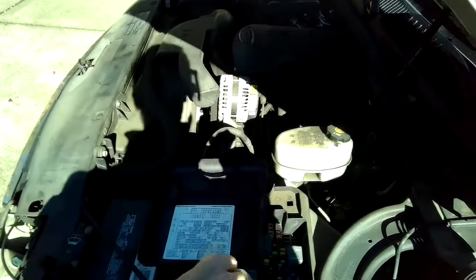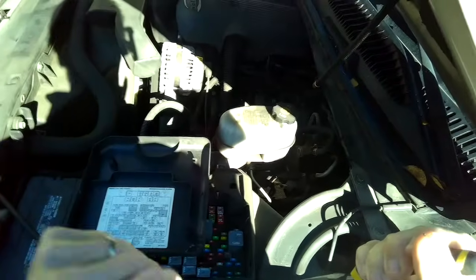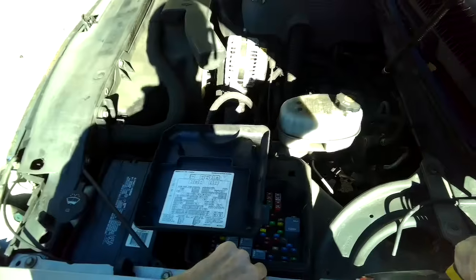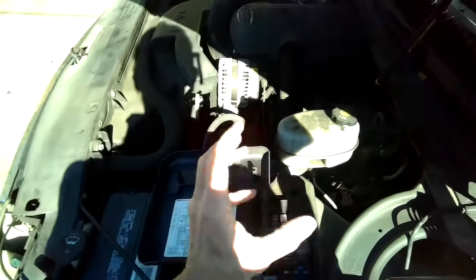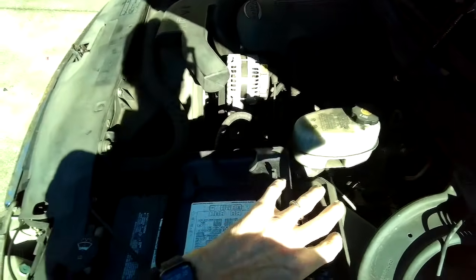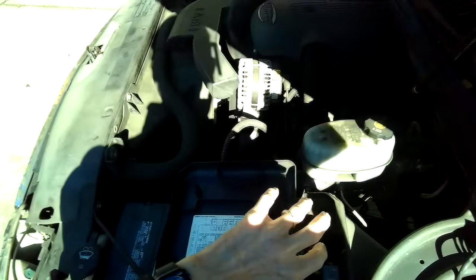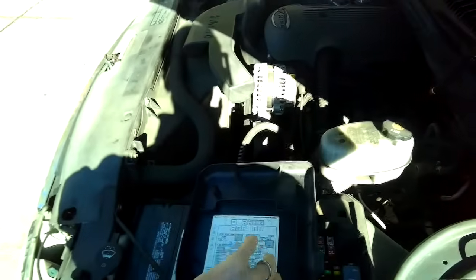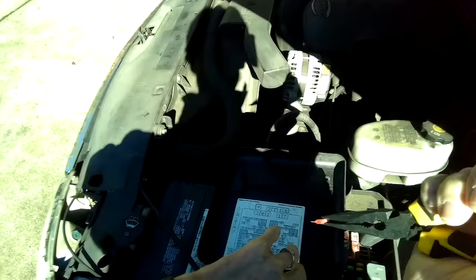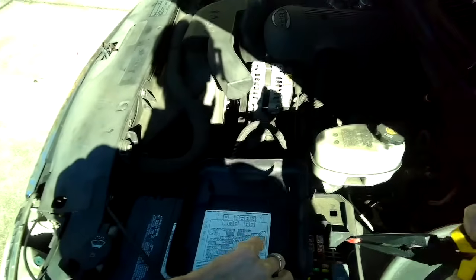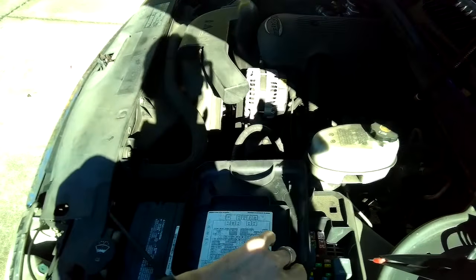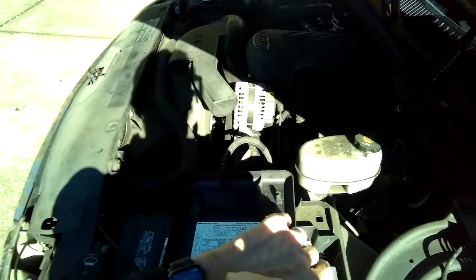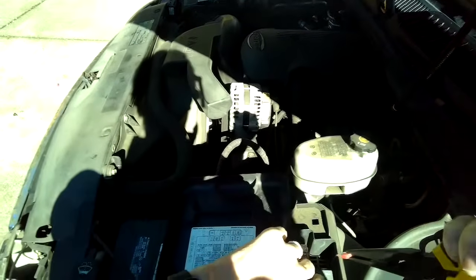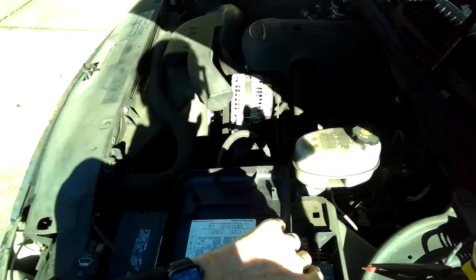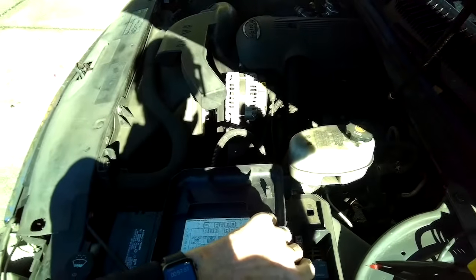Coming up on half a minute. This is a really easy procedure, and it'll fix a lot of problems with the HVAC system. Sometimes the actual actuator motors are messed up and need to be replaced, and other times it's just out of calibration. If the battery got wound down or got disconnected and you lose power to the computer, when you restart and put the power back, you're going to have to recalibrate the HVAC.